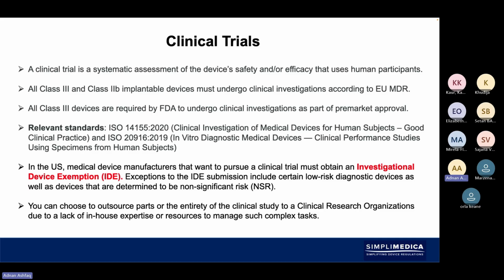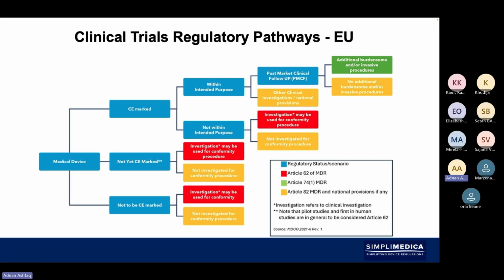that we might need to do, and we can compare a device that's already on the market with our device and then record the results that way, which is then viable data. And then the last method is clinical trials, where then you would have to then undergo the testing with human participants. If it's class 3 and class 2B implantables, then you need to undergo the clinical investigations, and then you need to follow ISO 14155 and then also 20916 for in vitro medical devices, in vitro diagnostics. In the US, you also need to follow the IDE exemption path and possible the PMA process.